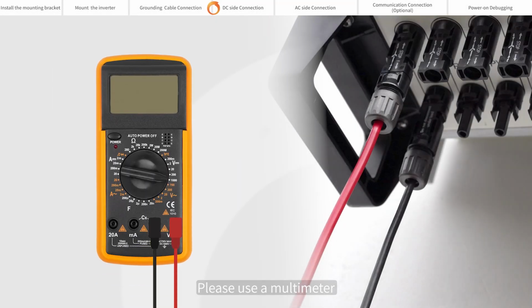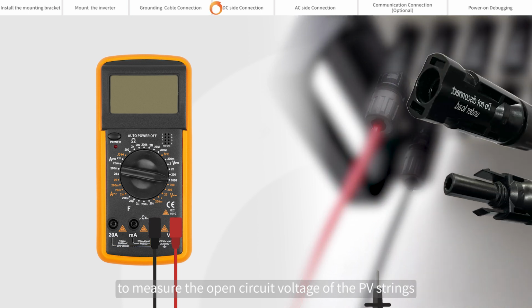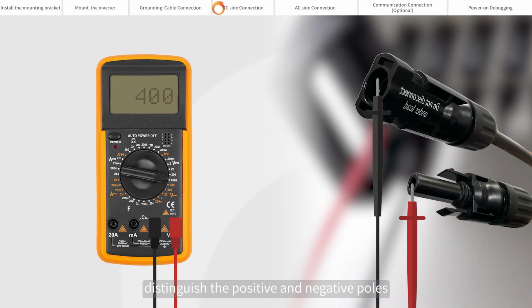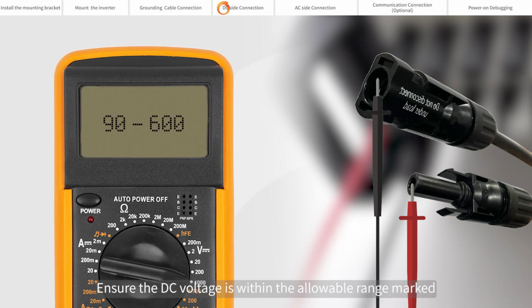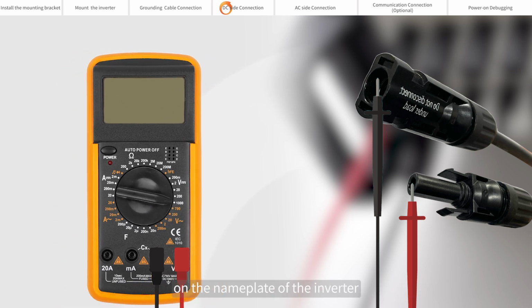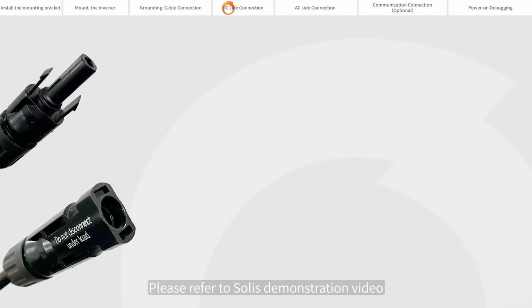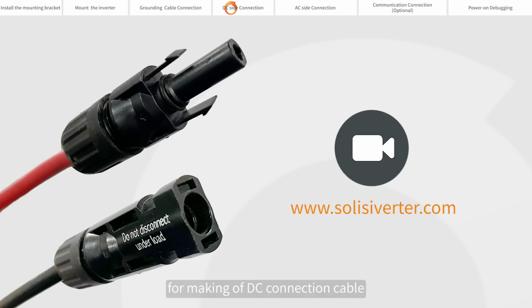Please use a multimeter to measure the open circuit voltage of the PV strings. Distinguish the positive and negative poles. Ensure the DC voltage is within the allowable range marked on the nameplate of the inverter. Please refer to the Solis demonstration video for making the DC connection cable.